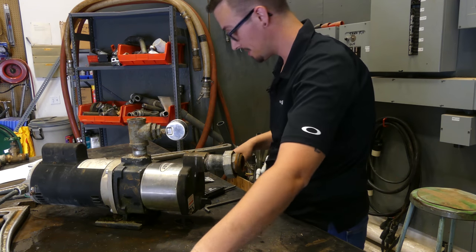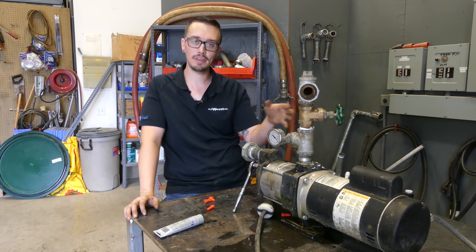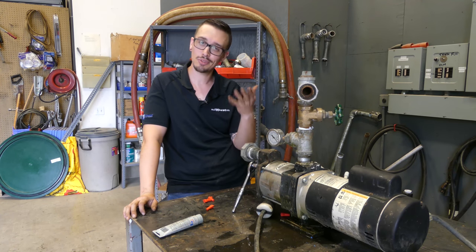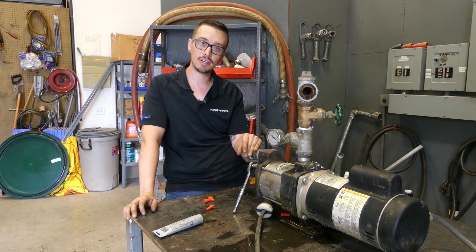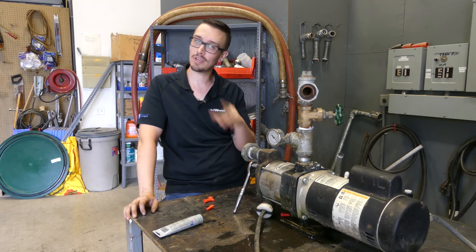The bolts should pull it in the rest of the way. We went ahead and called the customer back — he wasn't able to verify that the gate valve was actually functioning. So we think this one is just chalked up to a faulty gate valve. We did a quick water test — the pump tested great, we had good pressure. Nothing to be concerned about with this pump. We'll catch you next time — don't forget to like and subscribe. We're trying to put videos out as often as we can, ideally two a week, but right now about one a week. We've got tons of other pumps to test.